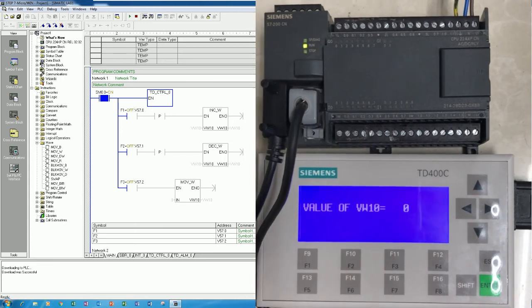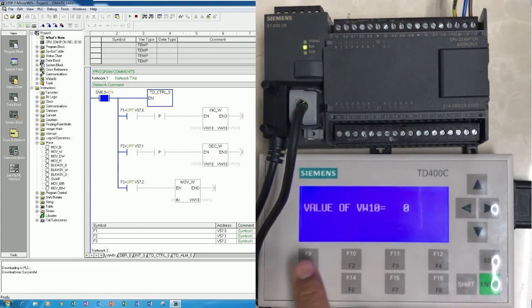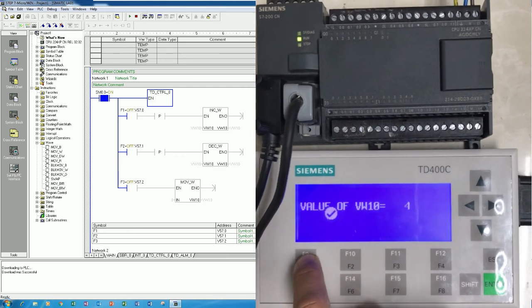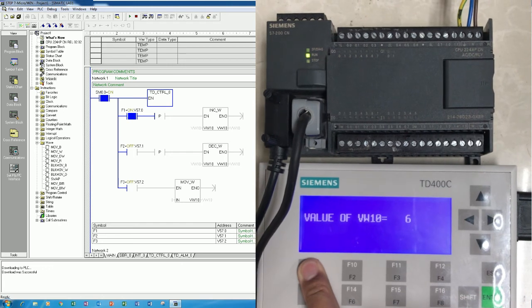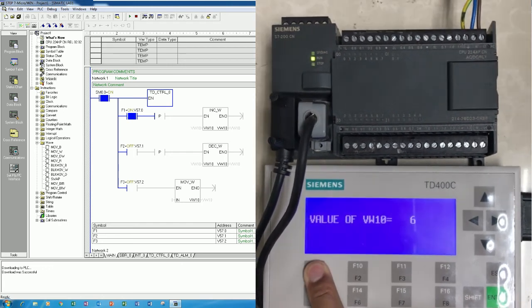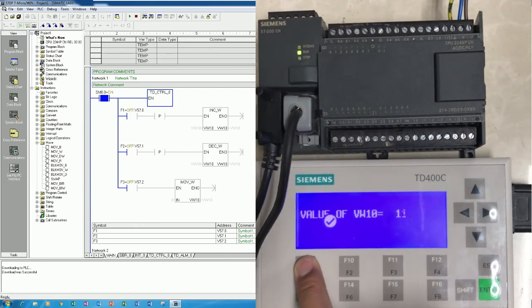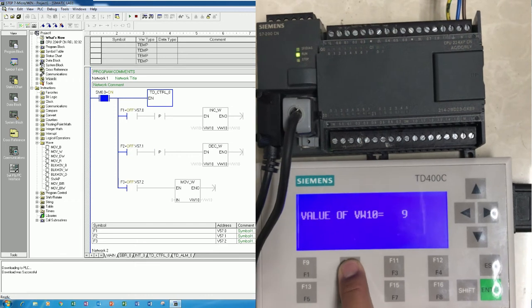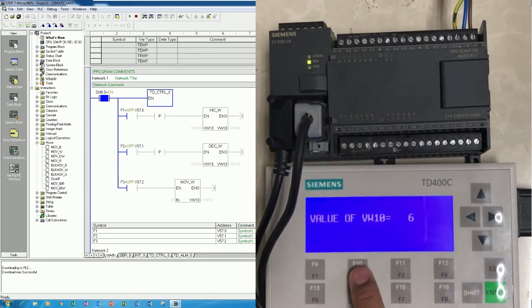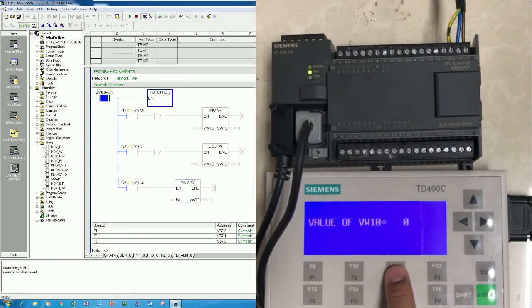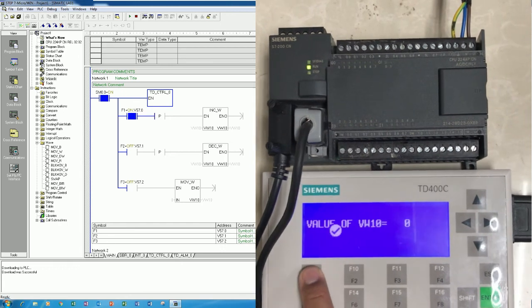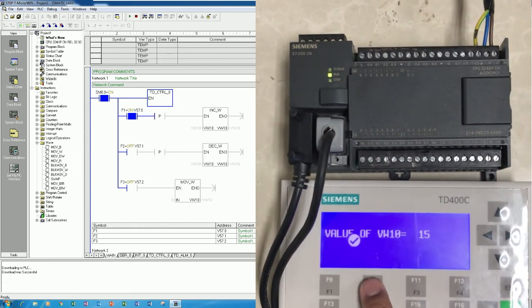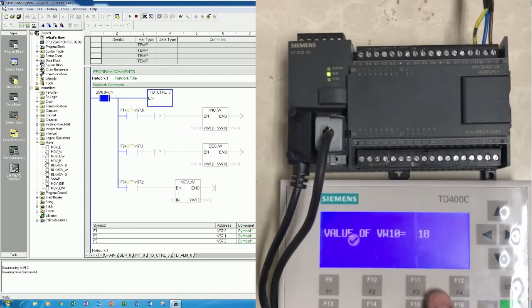The current value of VW10 is 0. If I press F1 it will increase, step by step. If I hold it, it does not keep counting because we used the positive edge contact. If I press F2 it decreases, and if I press F3 it resets to 0. Increase again, decrease again, and reset — it works correctly.